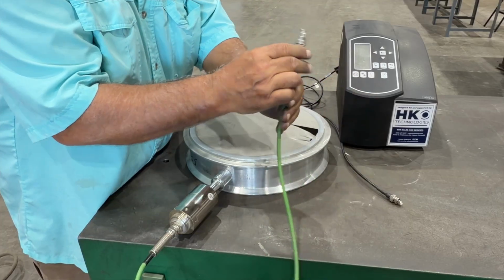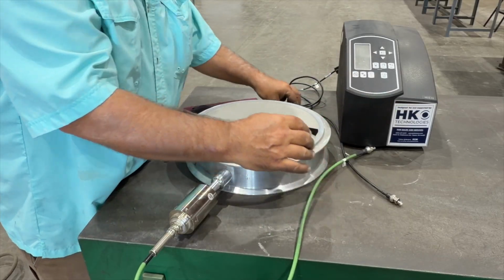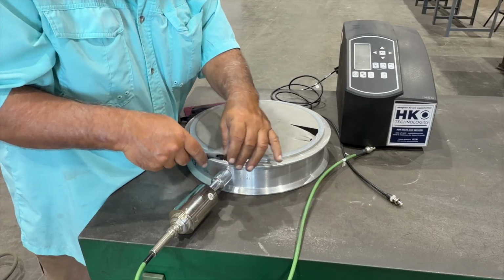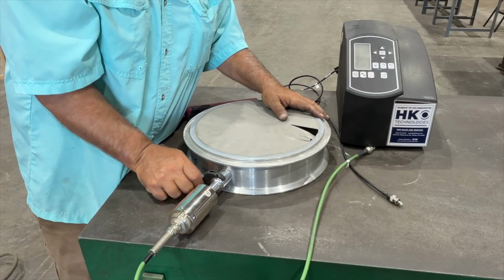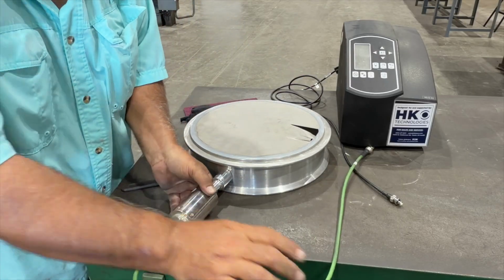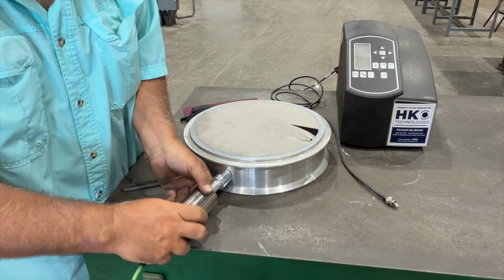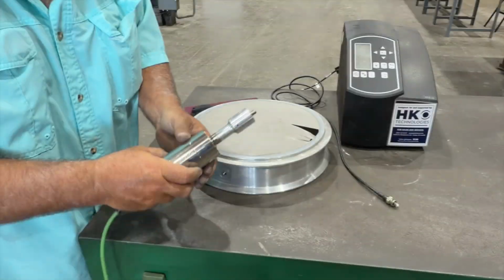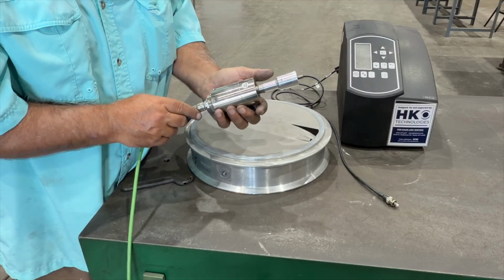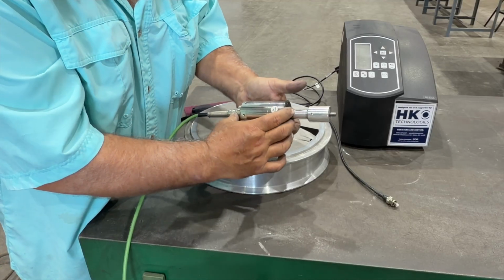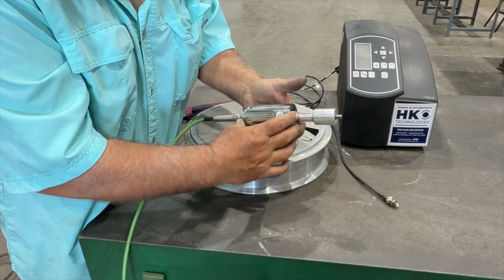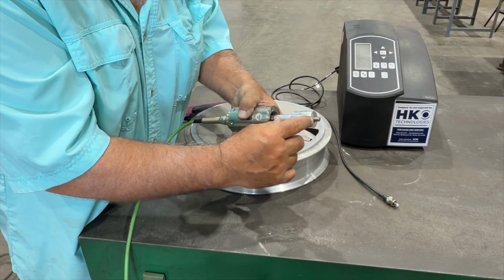First, unhook the pigtail. Spanner wrench to remove the ultrasonic transducer. Now we can inspect the ultrasonic transducer. This is the ultrasonic transducer or converter, and this is your ultrasonic booster.